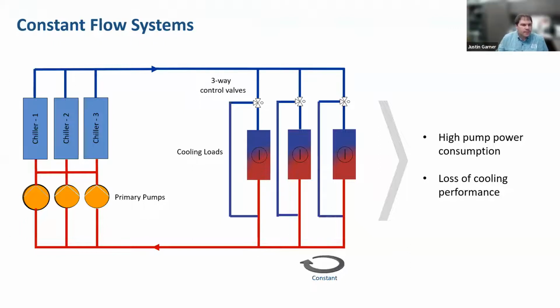Thanks, Pete. Yeah, so we're going to give a brief run through of the history of, in this case, chilled water systems. So up until probably, I'd say 15 years ago, this was a pretty common system. It's a constant flow system. Obviously, you can see here that you've got multiple chillers and primary pumps for the system. Those primary pumps would be constant speed. And then you would modulate your cooling loads using typically three-way control valves at each terminal. But the flow was always the same.